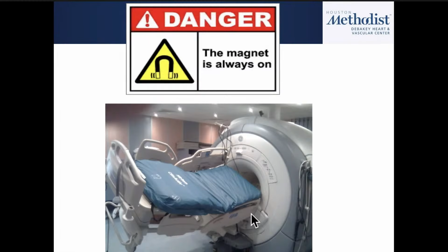And this is an example of what happened when somebody, not here, fortunately, somewhere, took a patient bed into the MRI room. You can see that the magnet acts as a very strong pull on metallic objects that are ferromagnetic. As it gets closer and closer to the magnetic field, it accelerates, and is able to take this entire bed and pull it up into the magnet. Also important, if you have a patient on the table and you take an oxygen tank, for example, that oxygen tank can become a projectile.